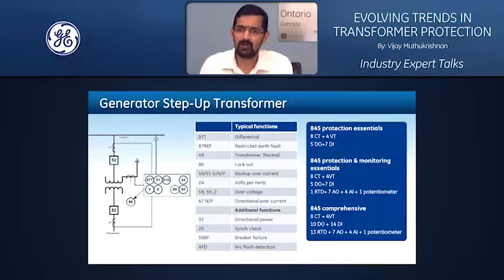The next application is also unique. Generator step-up transformers. You can view it in two different ways. The first is protecting the step-up transformer as a transformer alone, essentially. That's the first application I'm discussing. The majority of them are two-winding applications. In this case, you can also have a three-winding step-up transformer where you end up having two generators connected to one each of your medium voltage windings, and then you have a high voltage winding that is connected to your grid. This type of application also can be protected with 845. Whether it is a two-winding or three-winding, a similar approach will be adopted.